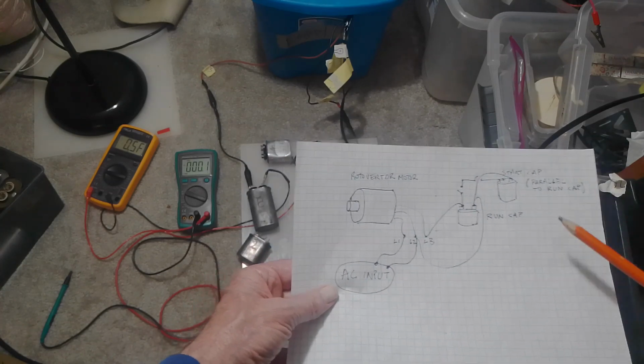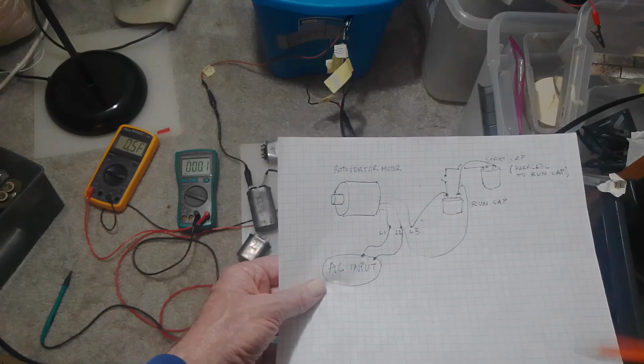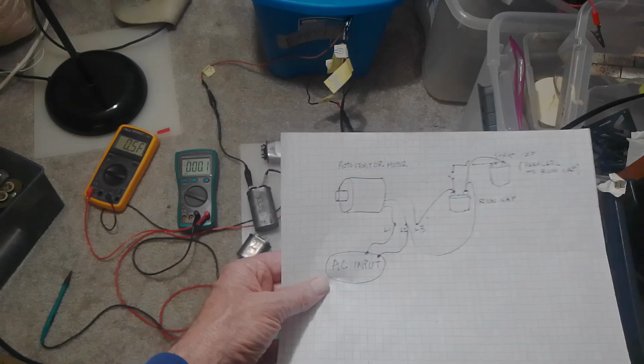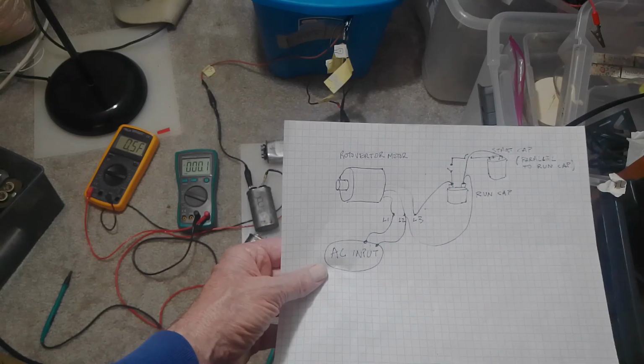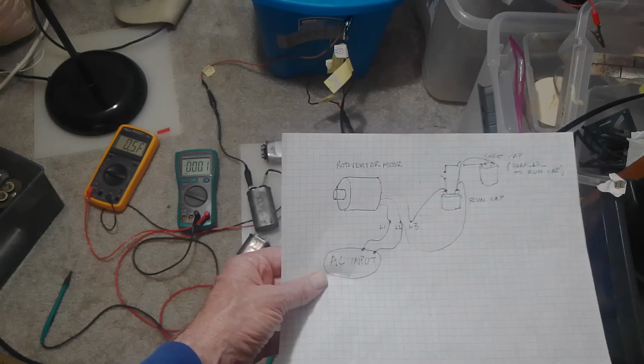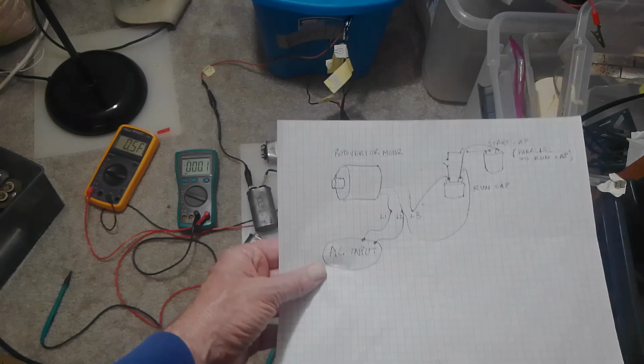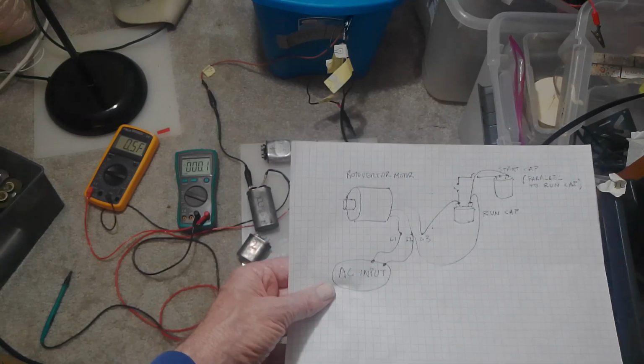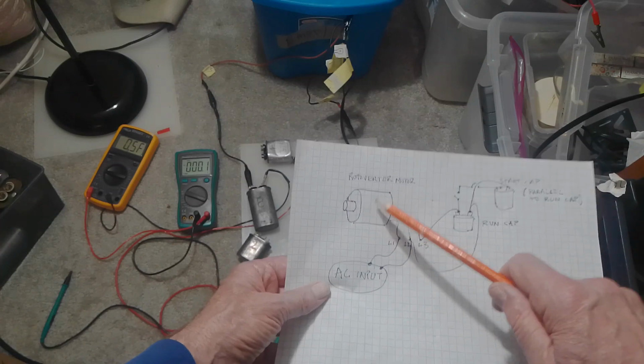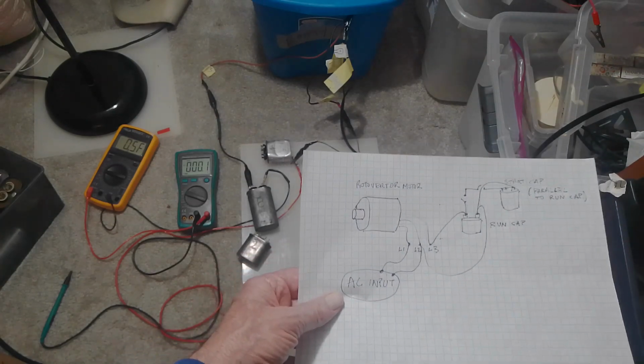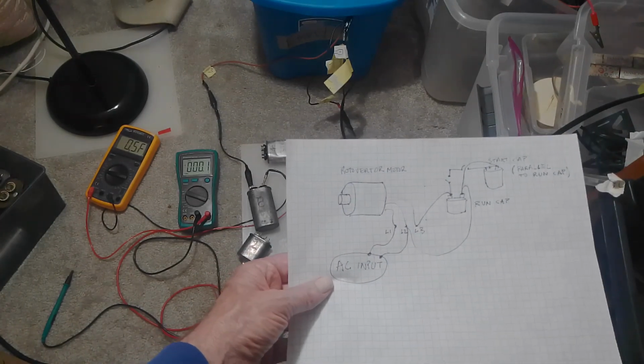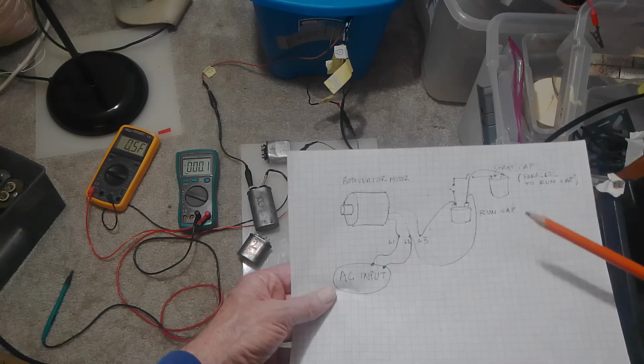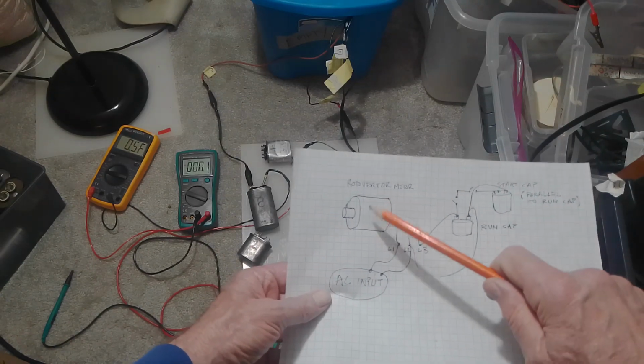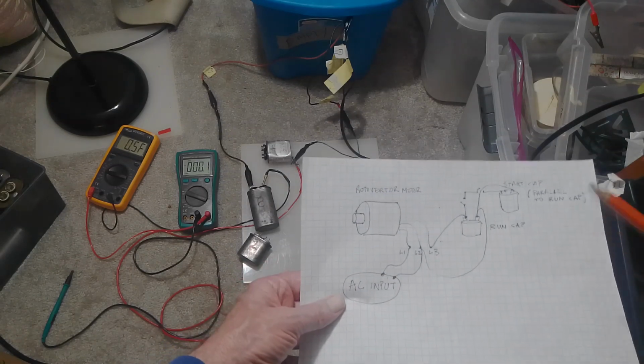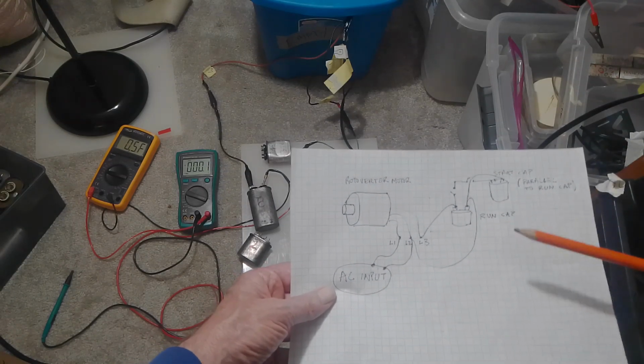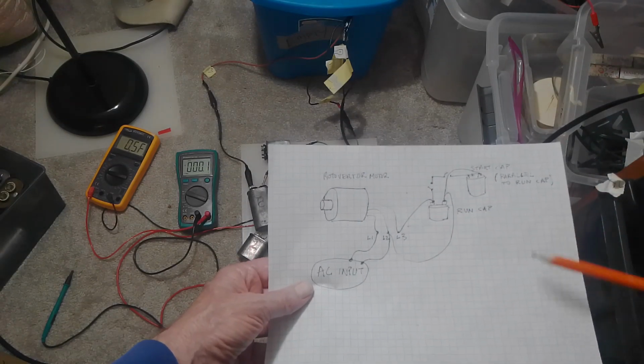circuit diagram, and your rotovertor will be hooked up in the WYE, they call it star also, configuration. And you want to have this in its high voltage circuit. Like you want to hook it up, it'll say on the label 460 volts, that's the way you hook up the motor. And then you run it on only 120, so it makes the draw very low.